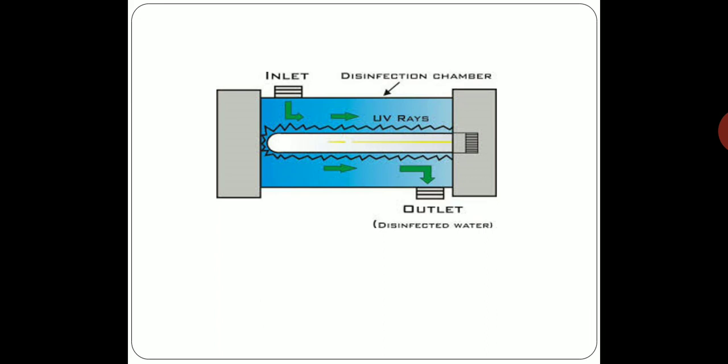You can see that in the figure. The destructive power of the rays begins in the blue-green region of the spectrum with a wavelength of 0.490 micron and increases in effectiveness to 0.149 micron. For disinfection to be effective, water should flow in a thin clear film close to the sterilizing ray.